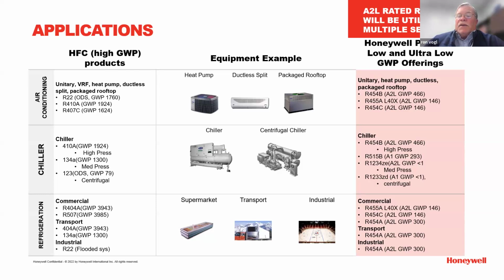The only point I want to make is in the chiller segment, a product you may not be aware of, 1234ZE. It is an A2L, less than one, and it's really finding its way into chillers, reciprocating type chillers. You can't go to an ASHRAE show without seeing that refrigerant in chillers. It makes sense, less than one, medium pressure, it's a 134A-like refrigerant, should be around forever, and a really good application there.